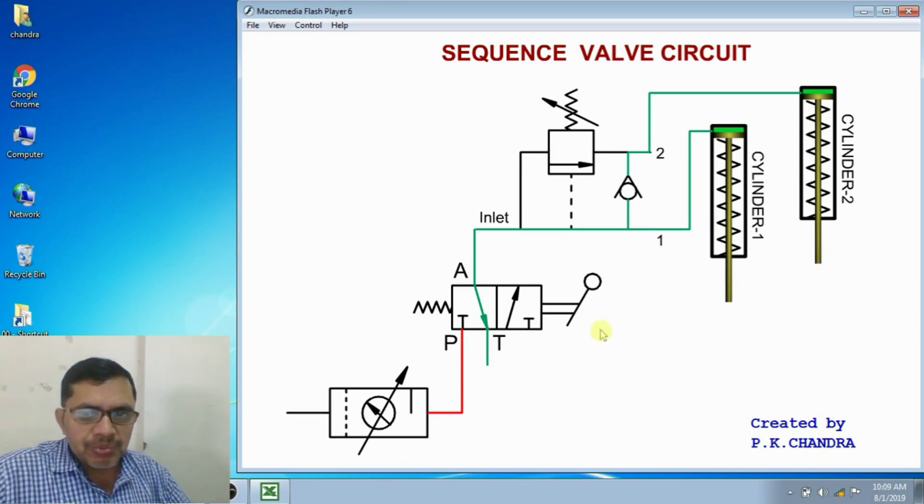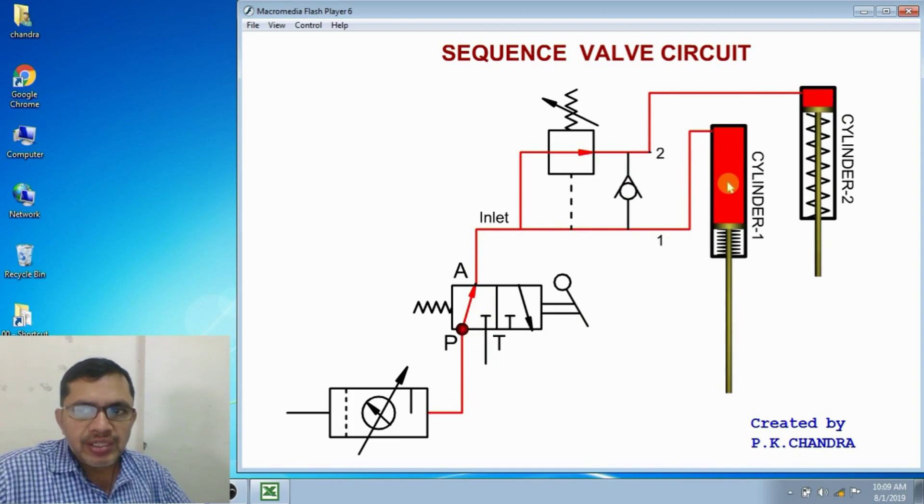When we keep the lever in the first position, P to A connection is there. Fluid flows to cylinder 1. Cylinder 1 will extend. And then after that, fluid flows to second cylinder. Cylinder 2 will extend. Means there is sequence in operation of these two cylinders. First cylinder extends first. The second cylinder will extend after completion of extension of first cylinder.